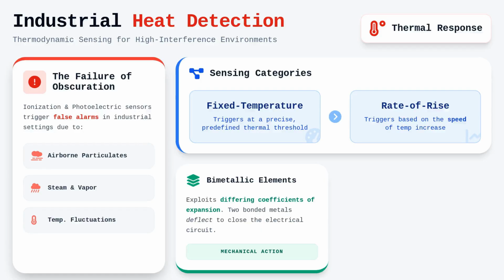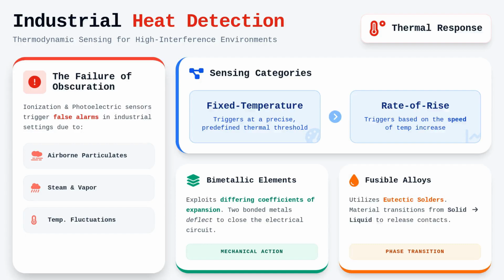A bimetallic element operates by exploiting the differing coefficients of thermal expansion between two bonded metals, which causes the element to deflect and close an electrical circuit once a predetermined temperature threshold is reached. Alternatively, fusible alloys utilize materials with precise melting points, such as eutectic solders, which transition from solid to liquid states to release a contact or a sprinkler bulb at a calibrated temperature. Understanding these material properties is essential for selecting the correct sensor for a given industrial process.